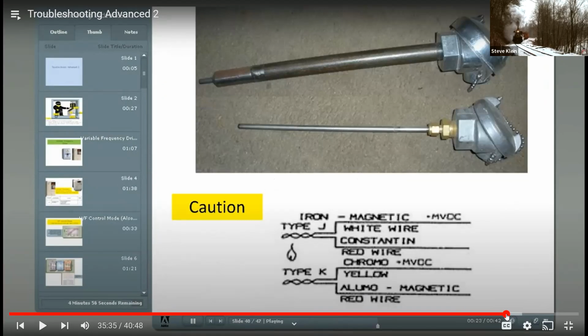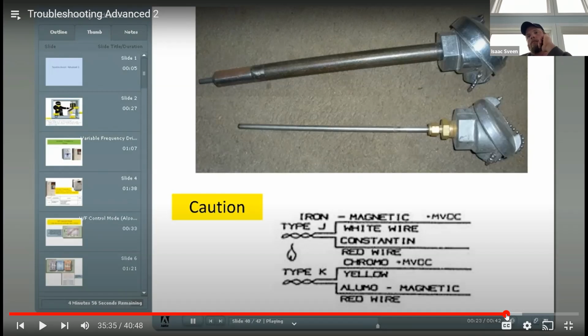Okay, guys, what the difference in these probes is that first one on top has got an extra chunk of 1/2-inch pipe, which is protecting the guts, which is kind of like that bottom probe. The bottom probe, if it's in airstream, is going to react much quicker because it doesn't have that extra 1/2-inch pipe to heat up. It's only got that 3/16 or 1/4-inch diameter tube to heat up and cool down.